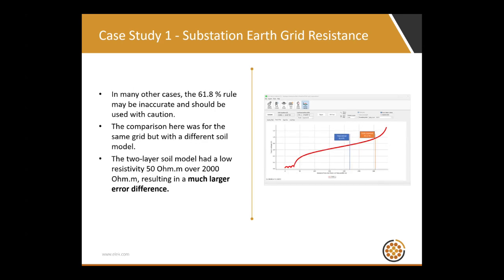Now, I'll show you a case where that rule is infringed significantly. We had the same model and the same test, and in a second, I'm actually going to hand over to Edston. He's going to show you how we set up this model in the software, and how we do the simulation. But in this case, we just changed the soil model. So we used a 2-layer soil model. Now that was a low resistivity over a high, so 50 ohm meters in the top layer and 2000 ohm meters in the bottom. And we saw the theoretical apparent impedance at 61.8% in comparison to the SafeGrid software actual apparent impedance. And we saw a large difference for that soil model.